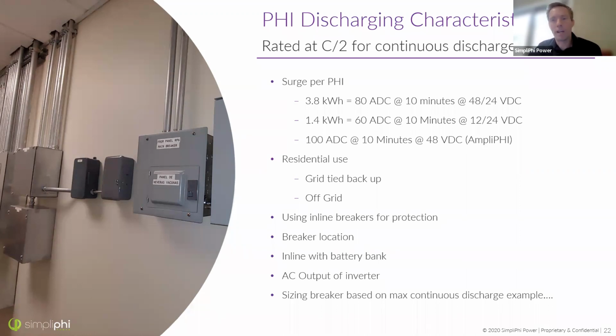Let's talk a little bit about protection. I just gave you the safe continuous discharge rate, and I just talked to you about the surge rate, the maximum rating that any of these batteries can give at any point in time. So how do we protect the batteries so that we don't over discharge? Using inline breakers, as I'm going to show you in the next few slides, is not really the safest way to protect your batteries. It's not a fail-safe. Systems need to be programmed and sized according to the specifications of the battery. I'll go into why. You can use breakers in line with battery banks.